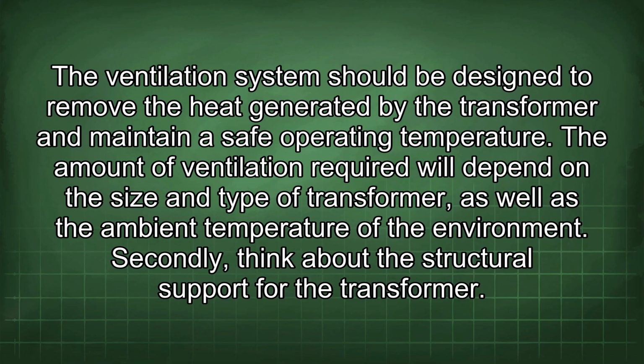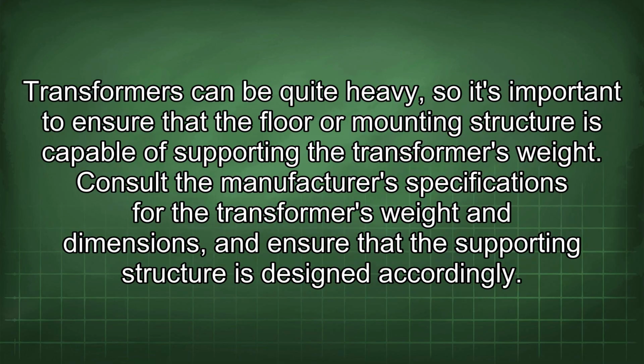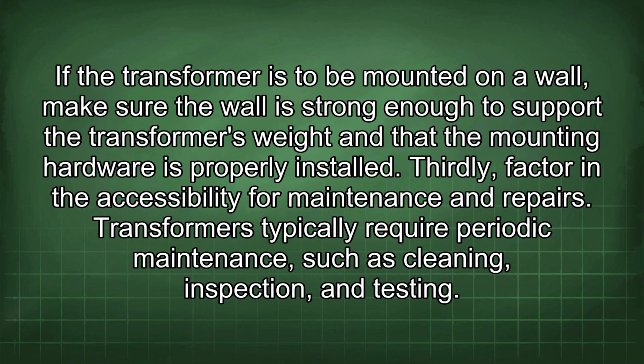of the environment. Secondly, think about the structural support for the transformer. Transformers can be quite heavy, so it's important to ensure that the floor or mounting structure is capable of supporting the transformer's weight. Consult the manufacturer's specifications for the transformer's weight and dimensions, and ensure that the supporting structure is designed accordingly. If the transformer is to be mounted on a wall, make sure the wall is strong enough to support the transformer's weight and that the mounting hardware is properly installed.